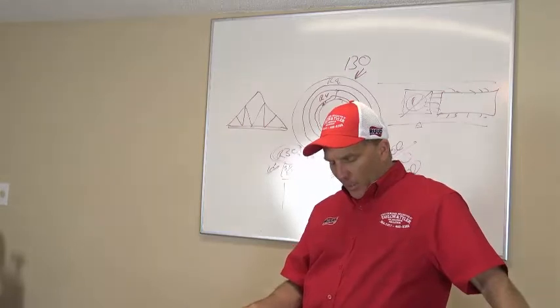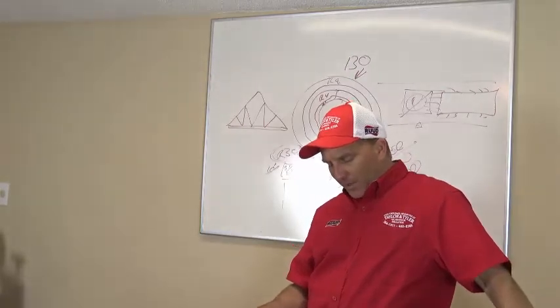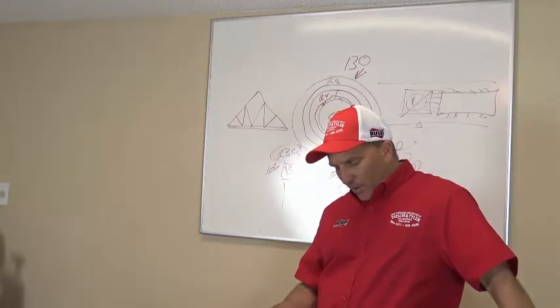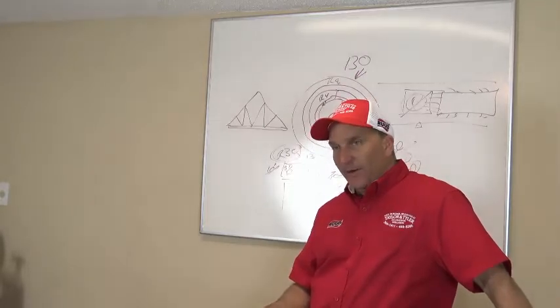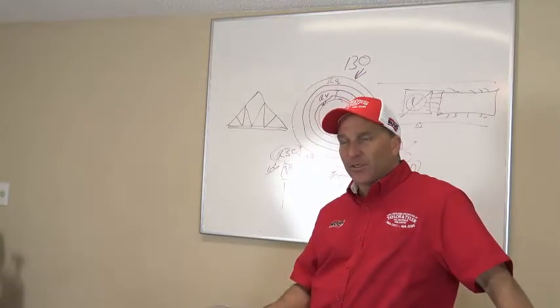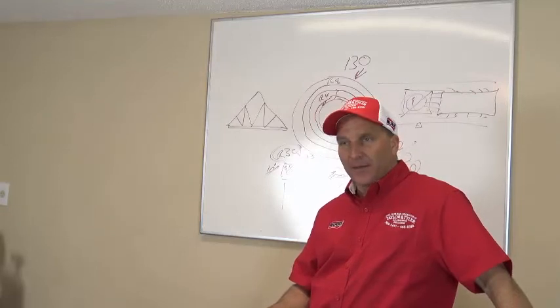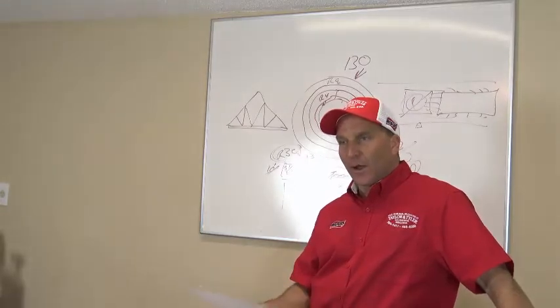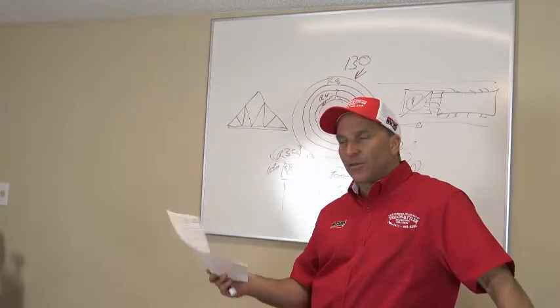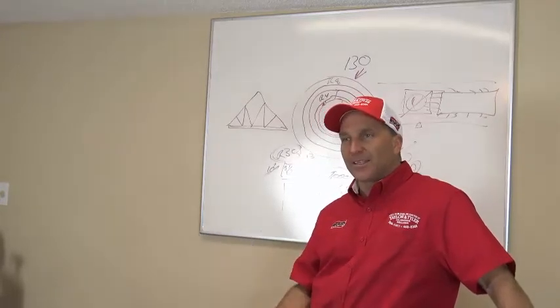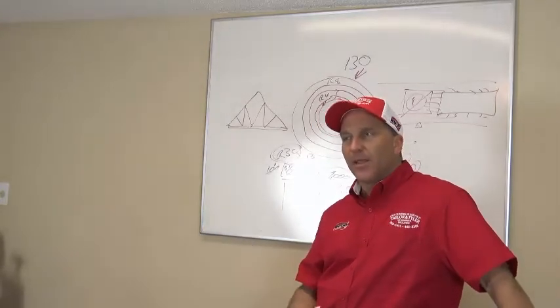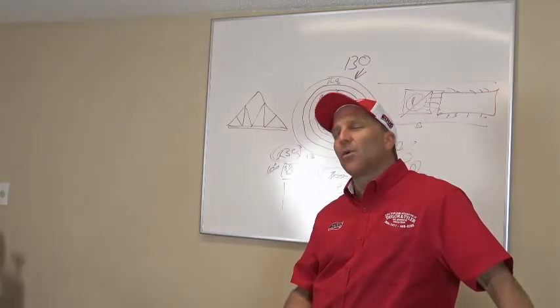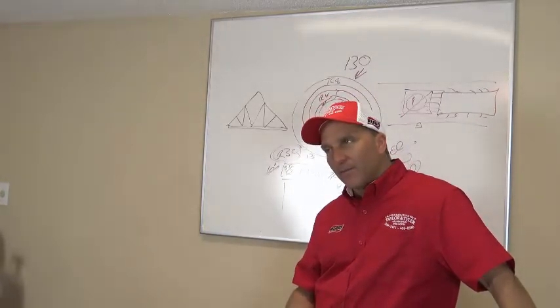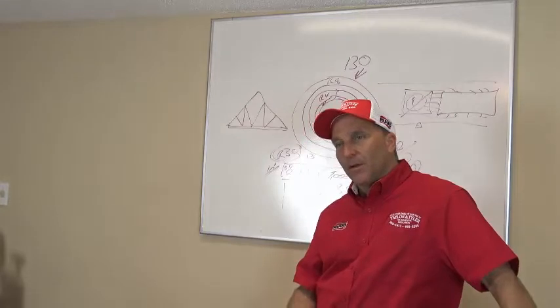All right, so blower cabinet. I want to know if your blower cabinet is dirty, filthy, or clean, right? Check it off there. Now, if it's dirty, you want to give a recommendation to clean the blower wheel and clean the cabinet, right? Vacuum it all out, pull your blower wheel out, clean the actual wheel itself, clean the dirt off of the blower motor, reinstall it. That's going to give you better airflow through the system. If your blower wheel is dirty, is your coil dirty, guys? Yep. Probably so.